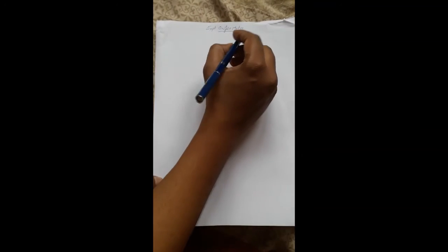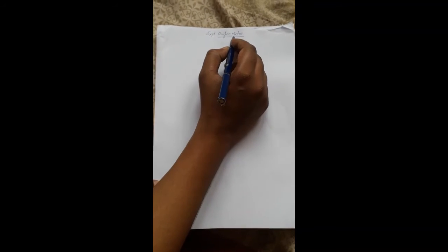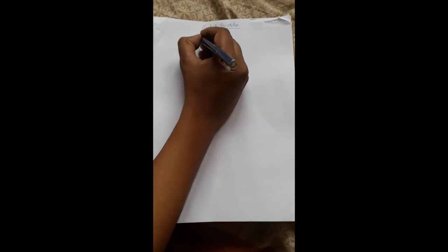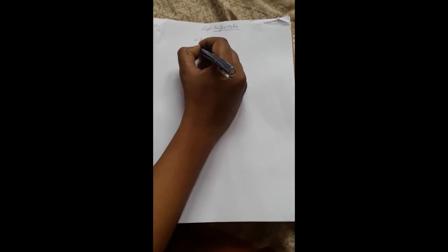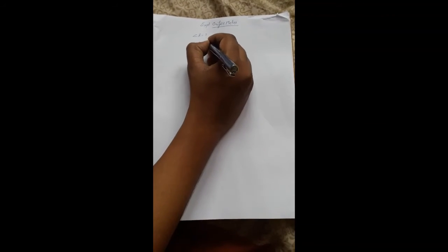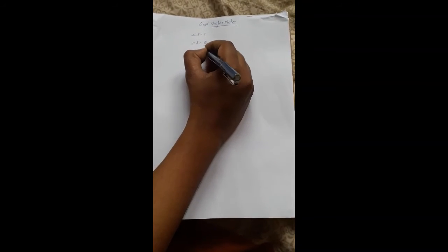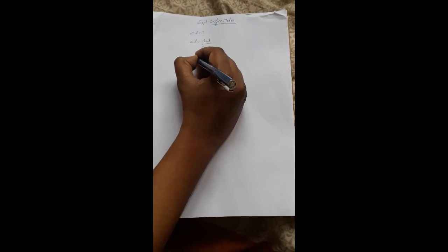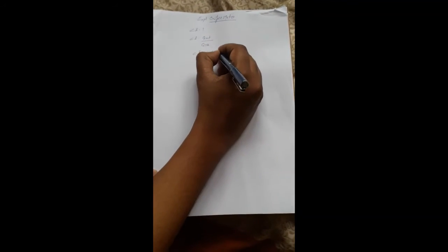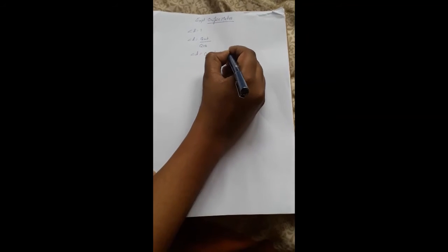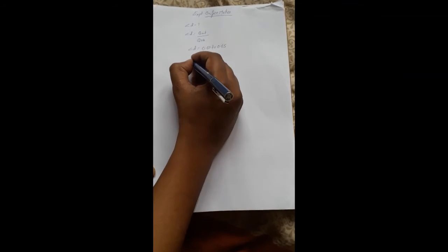Hi everyone. Today we are going to see the calculation regarding the orifice meter itself. In this, what we need to do is find out the CD itself. So CD is nothing but Q actual by Q theoretical. Okay. So the CD value should be in between 0.60 to 0.65. Okay. So Q actual equal to what?